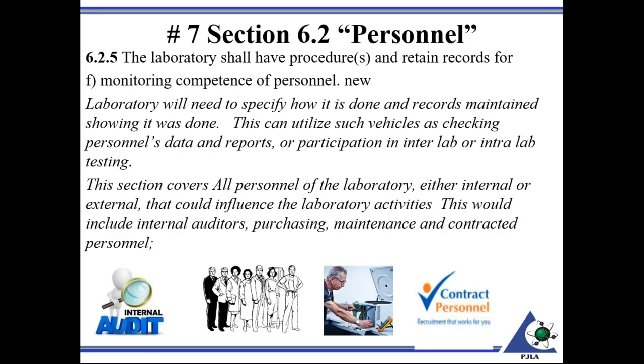Monitoring. So this is something new, monitoring the competence of personnel. Again, you would need to specify how this is done, and records showing that it was done. This could include such vehicles as checking personnel's data and reports. Proficiency testing is something that's required anyway. An organization is required to perform proficiency tests. Include your personnel in there. You can run your own intra-lab testing, for example, to check the uniformity of the results provided by your staff.